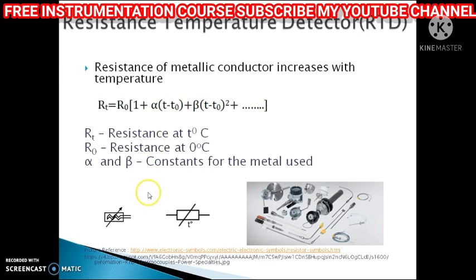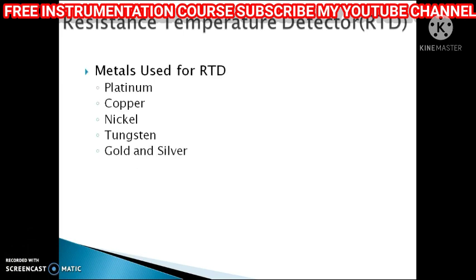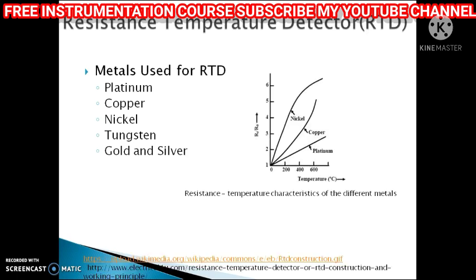This is the symbol of the RTD detector and this is how it practically looks. The conduction material used for RTD should possess high resistivity so that minimum volume is required for manufacturing. The noble metal platinum is used because it does not oxidize with the material being tested, and it also withstands a very high temperature range.